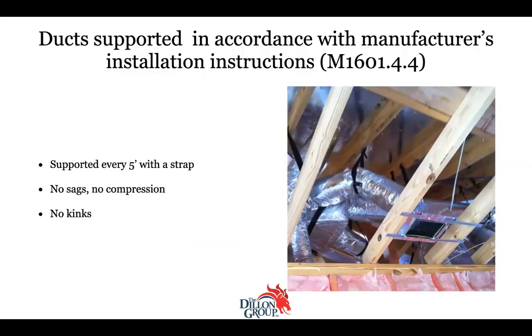And the ducts have to be supported in accordance with the manufacturer's installation instructions. We still see this. That's like supported every 5 feet with a strap or a saddle. No sags, no compression, no kinks. And yet, what do we see all the time? We see this all the time. It's not allowed under Energy Star. But if you see this and it's supposed to be an Energy Star home, you should give a shout out, because that tells us that the energy rater is not doing their job.